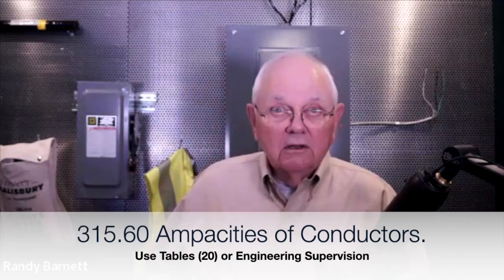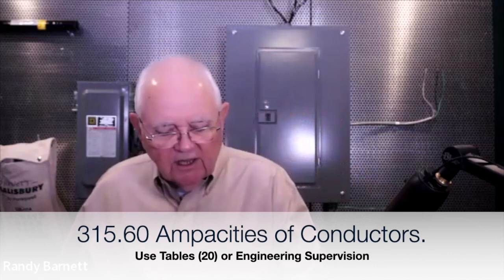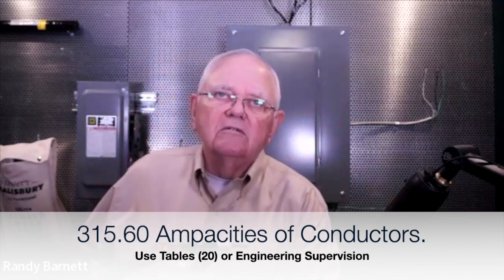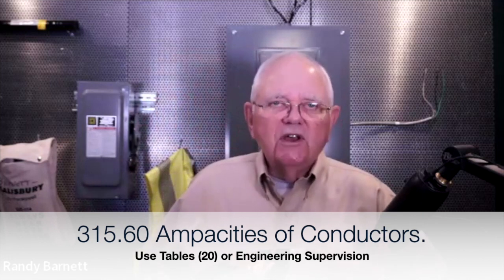As far as the ampacity requirements, there are 20 different tables for ampacity found in Article 315 on medium voltage cable. And it's all based on the type of conductors you have, whether it's triplexed in air, in a duct, or whatever it is. So you need to go through and look at the different requirements or applications that you would have before you could determine the ampacity. Also, there are tables in there for temperature correction, just like we would normally have to determine ampacity values. So that, in a brief nutshell, is medium voltage cable, Article 315.